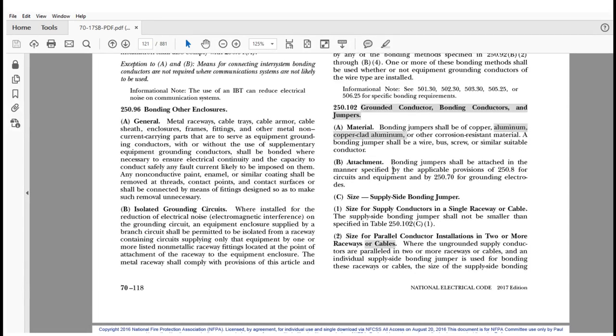So, you know, a lot of people argue where armor or aluminum is exposed to a corrosive environment, they don't understand that the aluminum can form a protective barrier, and that protective barrier is very hard. That oxide, aluminum oxide, is very hard versus a copper oxide, which is very soft, which can be scraped off very easily. Not so with the aluminum. You have to work at it. So it's protective, and so by adding aluminum and copper clad aluminum it just reiterates the fact that even bonding jumpers can be of those types of materials, not just copper, and they are corrosion resistant material. Okay, I wanted to make that very clear for that application.